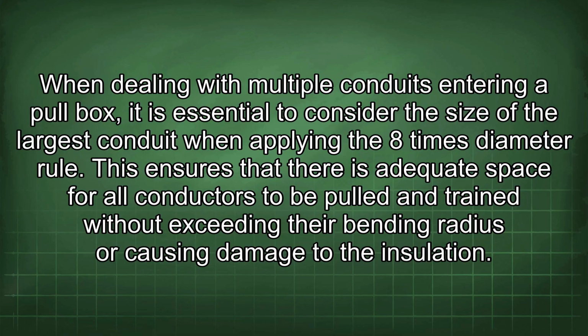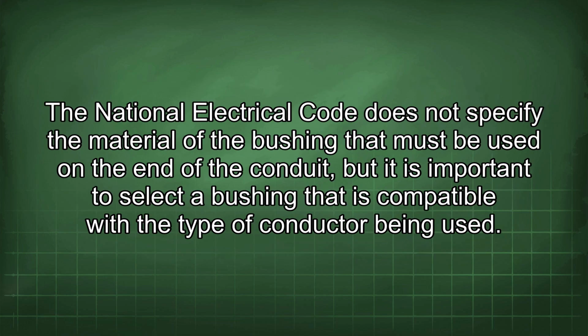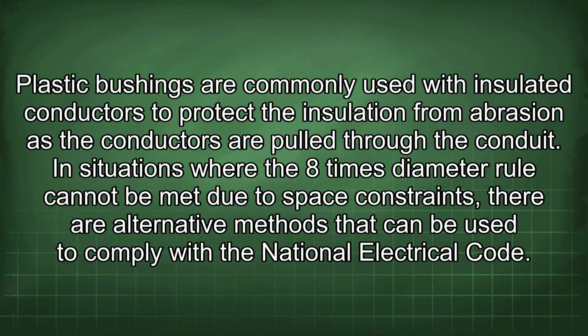This ensures that there is adequate space for all conductors to be pulled and trained without exceeding their bending radius or causing damage to the insulation. The National Electrical Code does not specify the material of the bushing that must be used on the end of the conduit, but it is important to select a bushing that is compatible with the type of conductor being used. Plastic bushings are commonly used with insulated conductors to protect the insulation from abrasion as the conductors are pulled through the conduit.